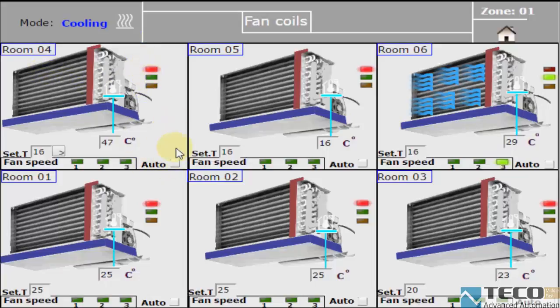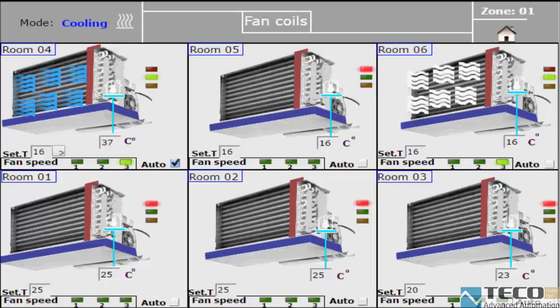Let's run room number four and check the auto mode. We see that the system chooses speed number three for the fan speed. It's calculating the difference between the set point and room temperature — after that it selects number two, then number one. Here we see that the indicators become white, because the room temperature and the set point are now equal.